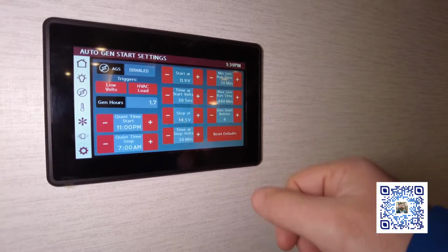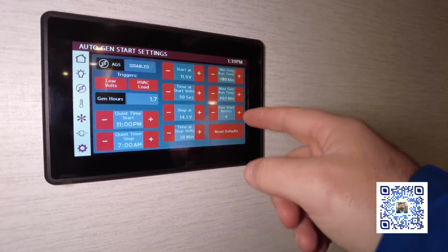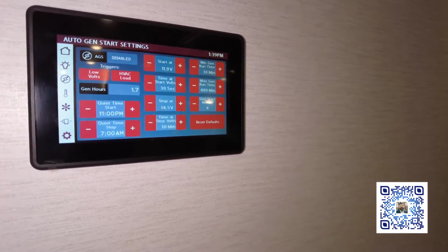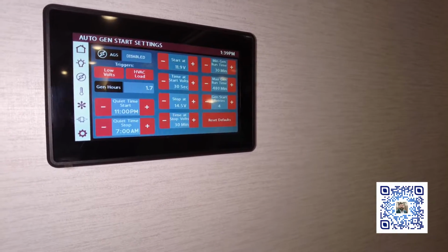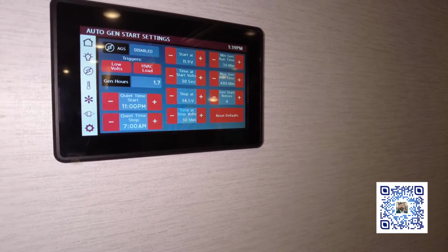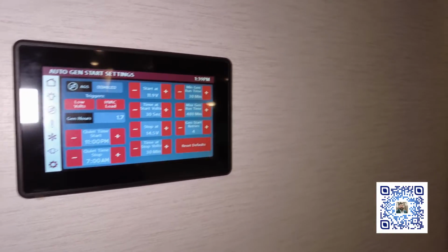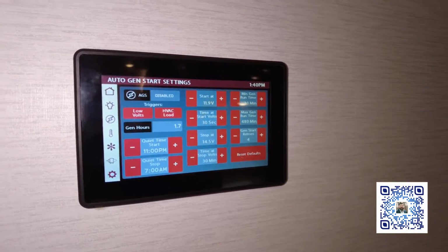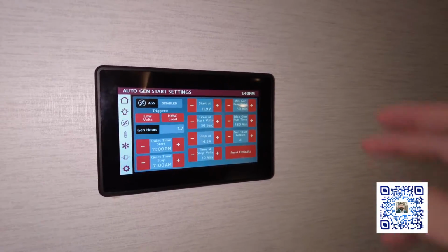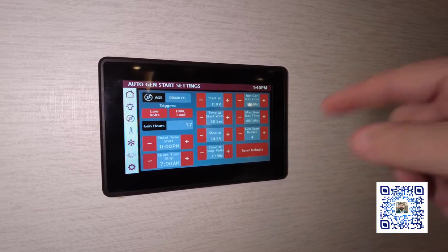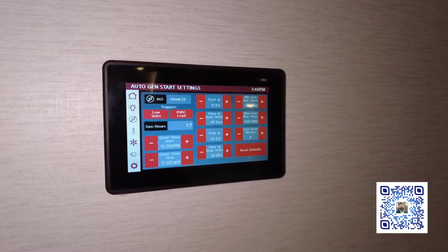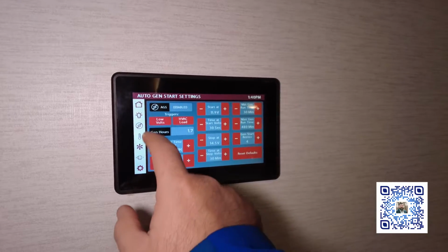Of course there's also maximum run time and generator start retries. The one thing the generator does not know is how much fuel is in the tank. It's simply a tube that goes into the tank and doesn't touch the bottom, about a quarter tank shy. So for whatever reason, if it's not sucking fuel, the generator doesn't know it. If it doesn't start after 4 tries, it'll quit trying. It's just not going to crank indefinitely and run your batteries down.